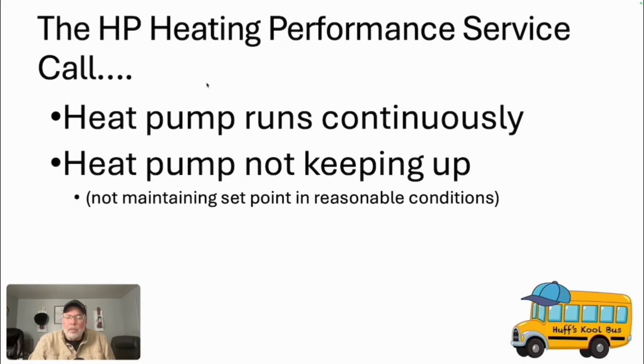Now, before you ask the question, what about load calculation? Well, we should be doing a load calculation on every job. However, a lot of times I was called out to jobs where a load calculation had not been done. A lot of times they replaced the equipment with the same size that was in their previous, and we can have a different conversation about that. I'm all about doing load calculations. However, many of the times I had to go out on jobs I didn't have that information, but that did not change my approach, because my approach has to start with what is the system doing. When I say what it's doing, I mean what do we actually measure as far as delivered capacity, and what is the system capable of delivering? And then once we determine that, then we can branch out and talk about whether the system is sized correctly or things like that.